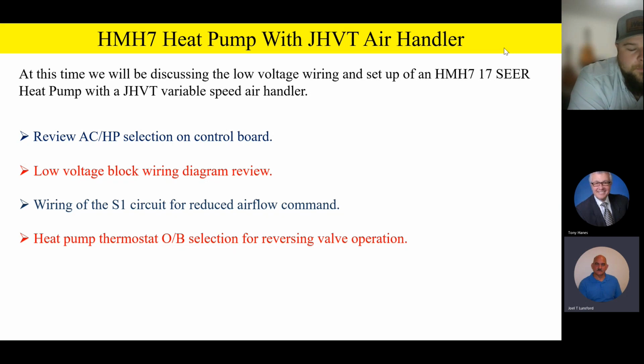In addition, we want to make sure that we understand that not only do we not have to use a relay kit, but we also have to have a thermostat that has a BO selection for reversing valve operation. Now, while we're talking about thermostats, I don't have it on the PowerPoint here, but let's make sure that we stress too that whatever thermostat we select, we want to make sure we have the OB or the BO selection on there. But we also want to make sure we run a hard common wire to the thermostat. We don't want a thermostat that has a power stealing feature. I know some of your Nest and some of your ecobee thermostats, if you have the capability of pulling that common wire, you've got to be sure and pull that common wire, because if you don't and you have a power stealing setup, what can happen is the thermostat can actually cause some erroneous codes to be thrown on the board outside.